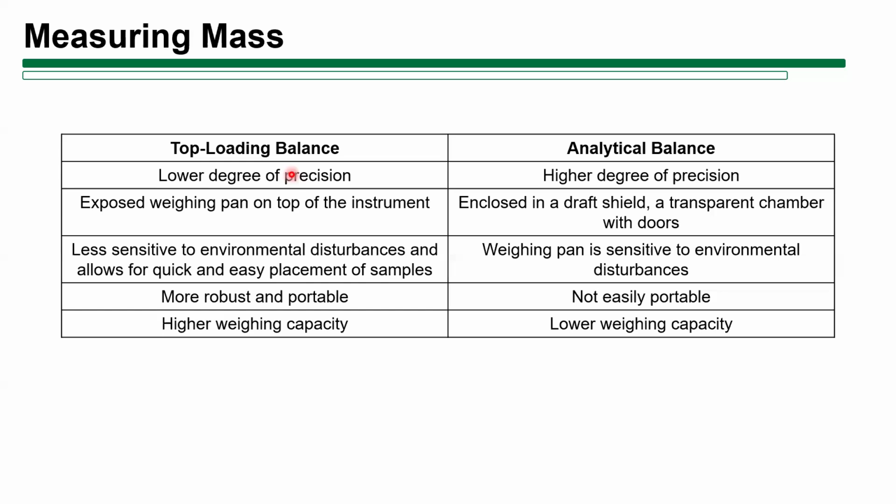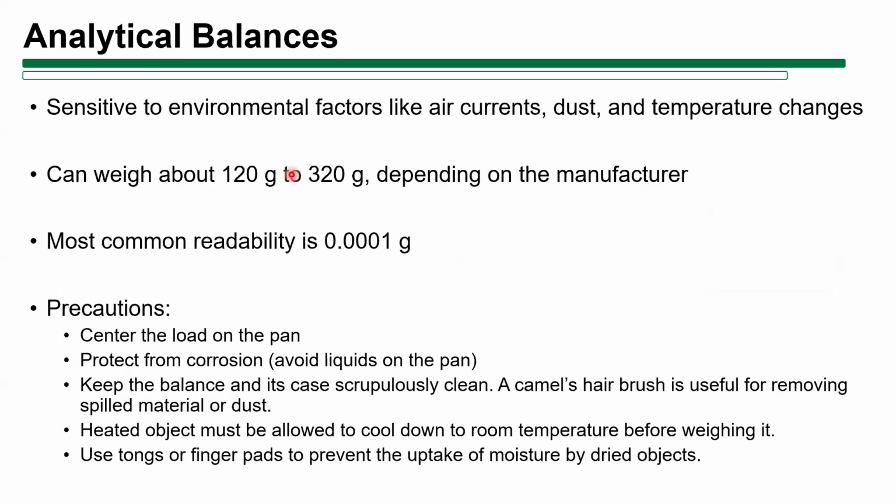The top loading balance has higher weighing capacity, while analytical balance usually has lower weighing capacity. Okay? So we usually do not put large beakers in analytical balances because large beakers have large weights which your analytical balance cannot tolerate or accommodate. So as I've said, analytical balances are sensitive to environmental factors like air currents, dust, and temperature changes. We will be talking about temperature changes later.